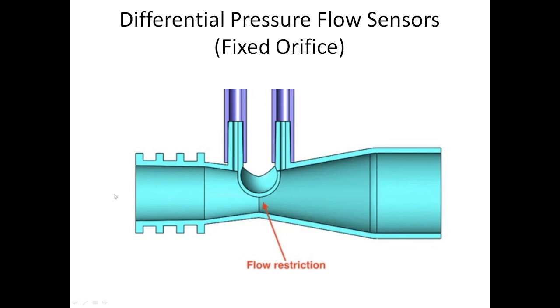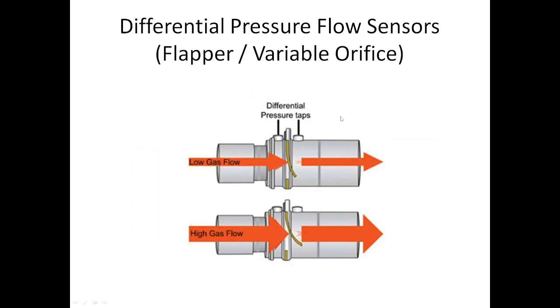The pressure would come in on the left side. It would go across this flow restriction, which is also a curved surface, and it creates a low pressure side over here. So the faster the flow through here, the bigger the differential is going to be between one side of the flow restriction and the other side. And that is pretty much it for a fixed orifice.